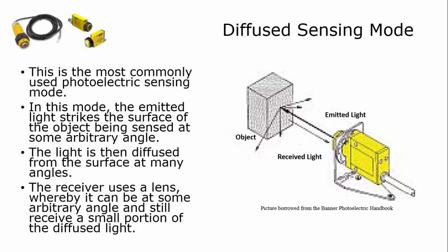In the diffused sensing mode, this is the most common mode used in sensing. The emitter and the receiver are in the same housing and the emitter sends out light that strikes the surface of the object being sensed. Once the light strikes the object, it is reflected off at all kinds of arbitrary angles. As long as some of that light gets back into the receiver, this sensor will see that the object is present.